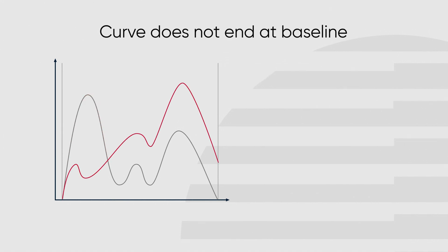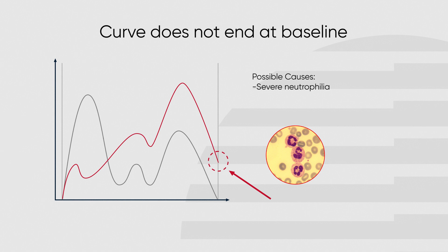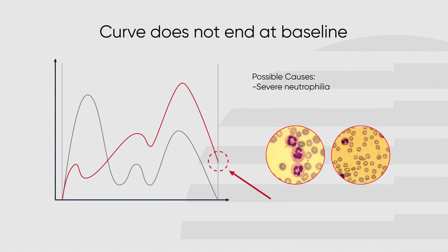If the curve does not end at the baseline and instead displays an abnormal high at the upper discriminator, this could be due to severe neutrophilia. In this example, the neutrophilia is due to CML (chronic myeloid leukemia), which can also result in an increase in myeloid cells. The reason is that the extreme amount of white blood cells clusters, making it complicated for the analyzer to read them one by one.